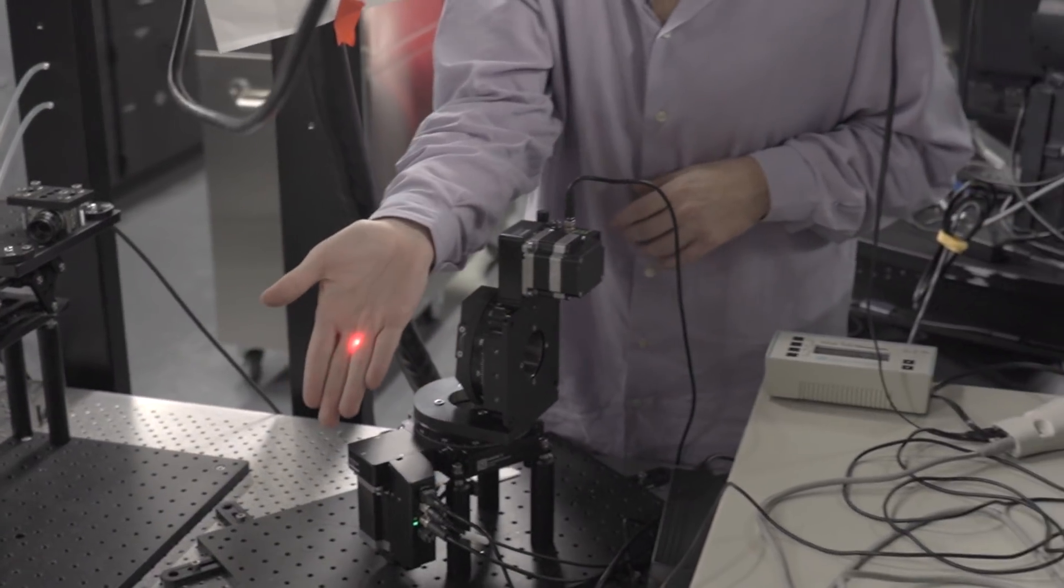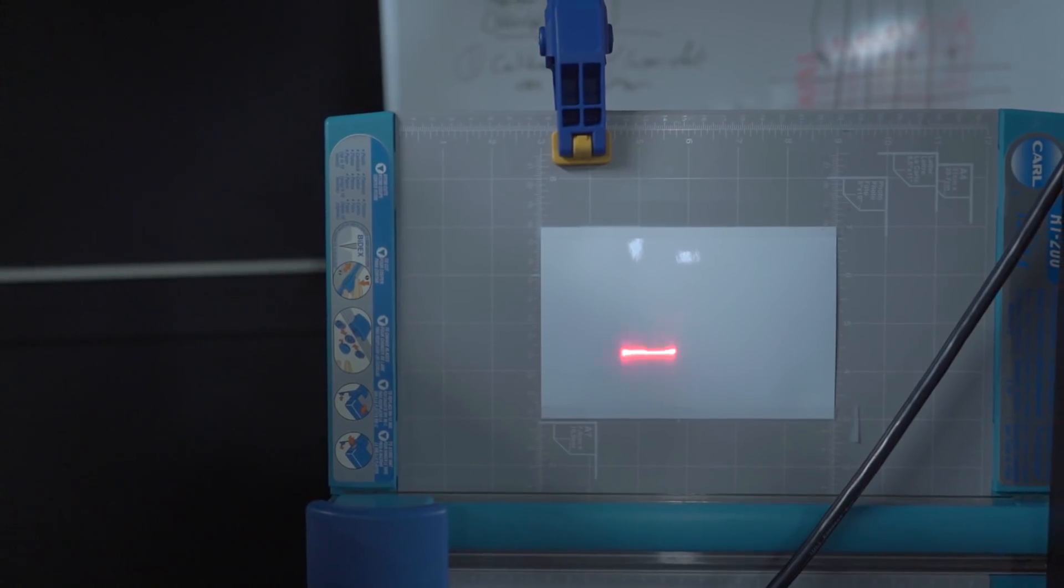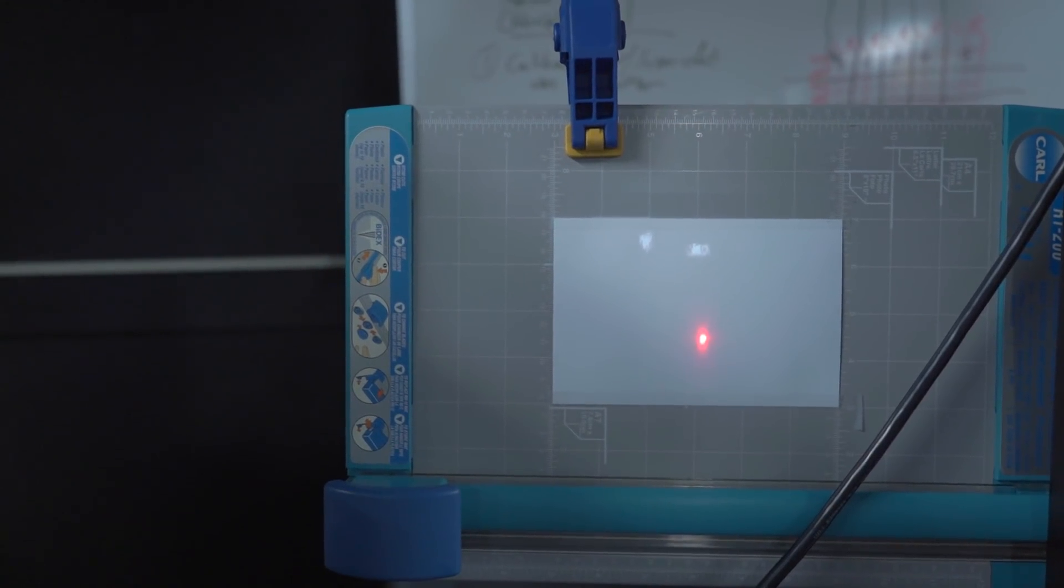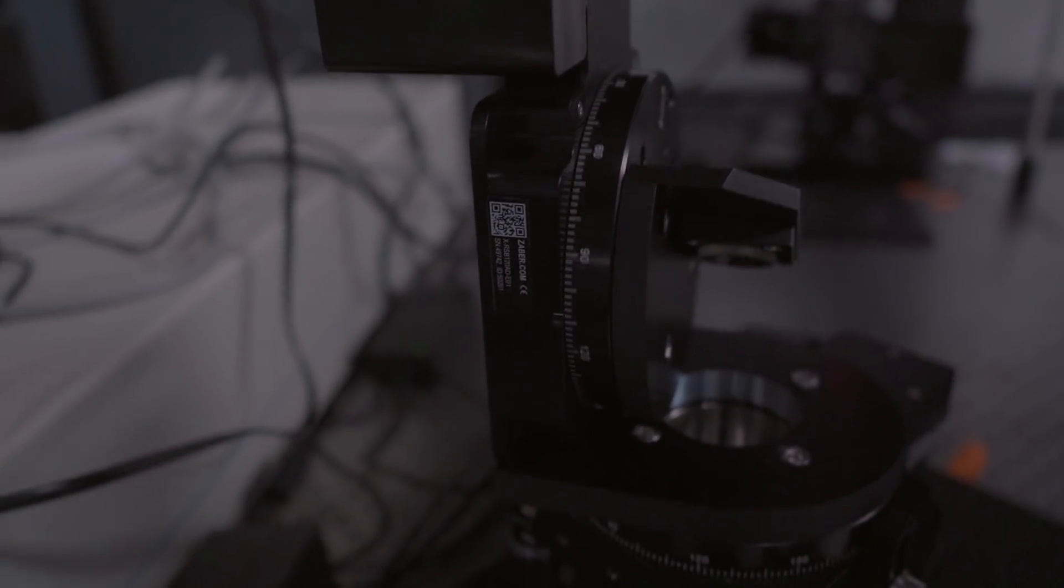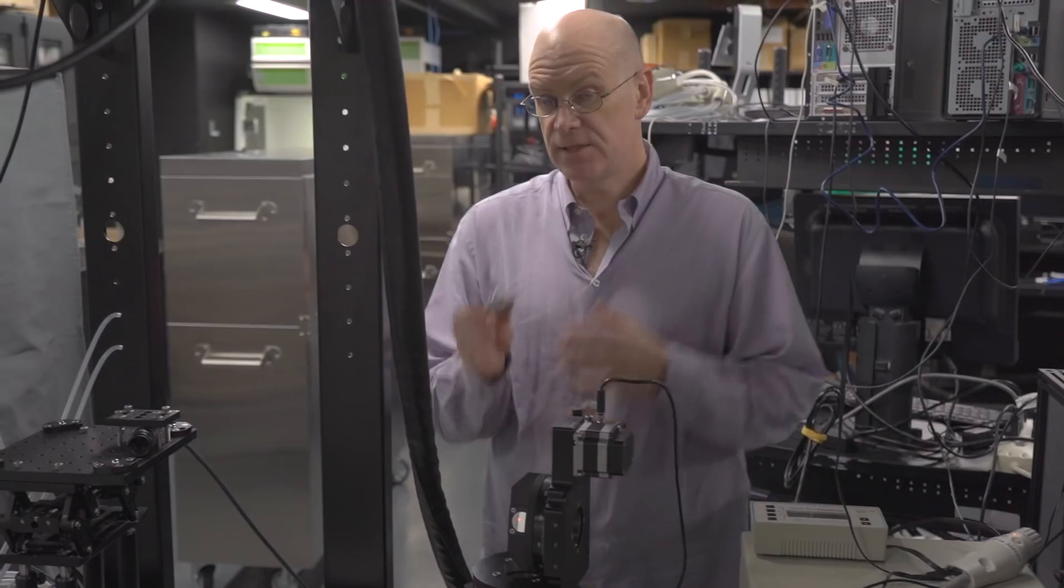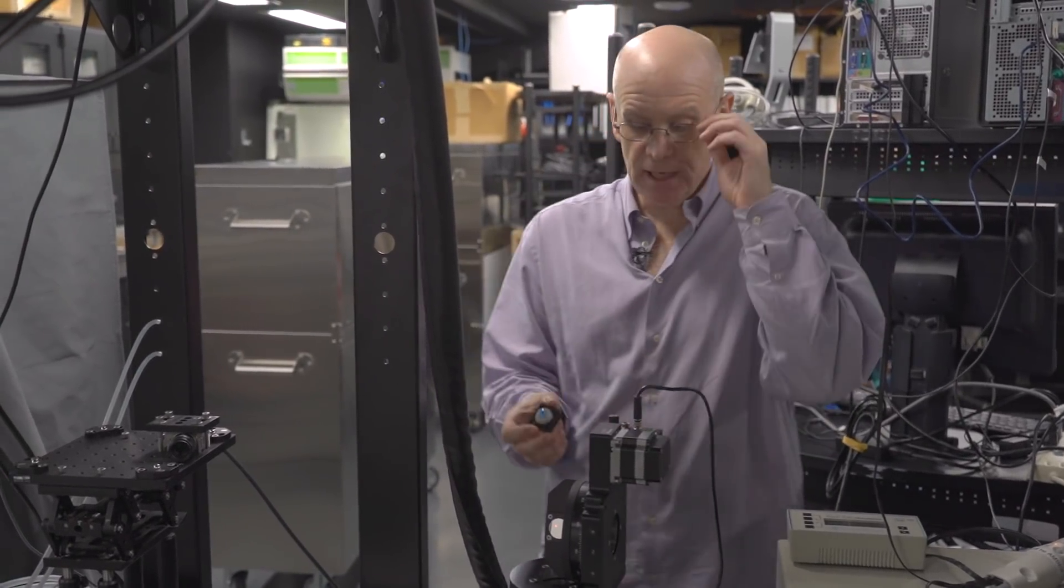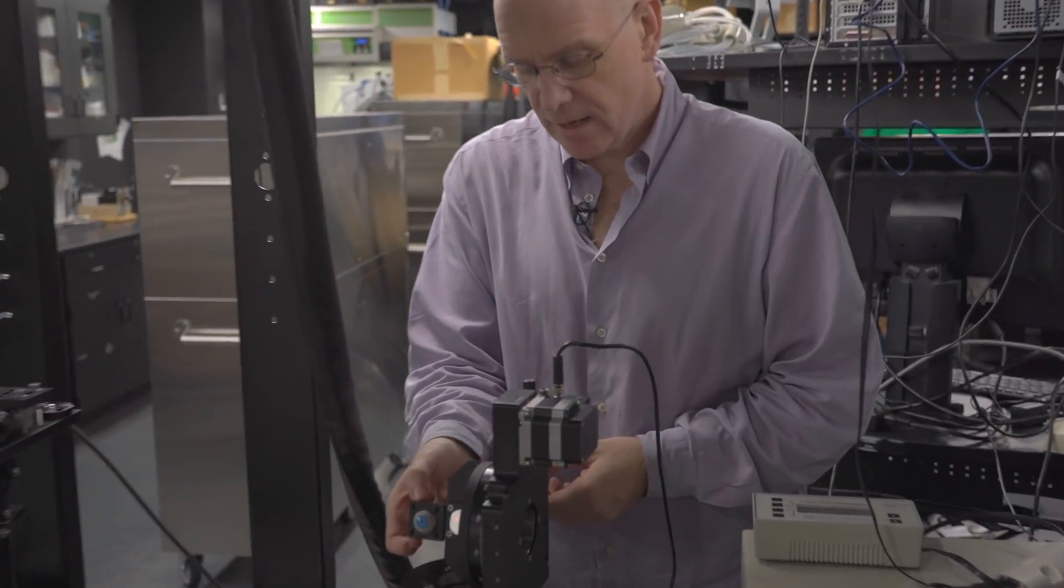Once we have actually calibrated the system and we know exactly how it moves, and that we can make motions that are smaller than what a human eye could actually do, we're now ready to calibrate modern eye trackers against the system. So we take the mirror off and we put now a human glass eye on there.